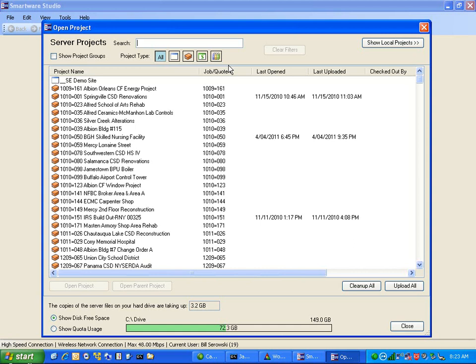It wouldn't work. The upgraded jar file looked like it was a completely different manufacturer's jar file, so it made it very, very difficult. And that's where the jar file switch tool came in, because we found that we had some jobs with these older versions, and as a service technician, you couldn't work on your job unless you can match your Smartware jar file version on your laptop with the Smartware jar file that was in the UNC.